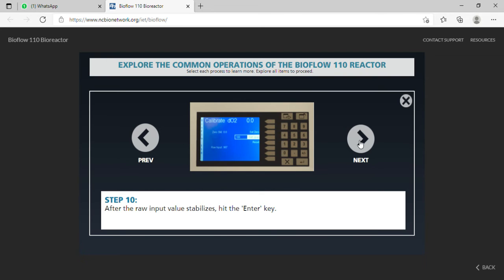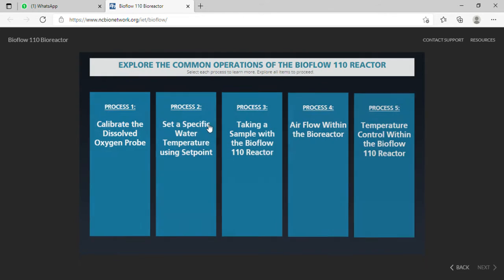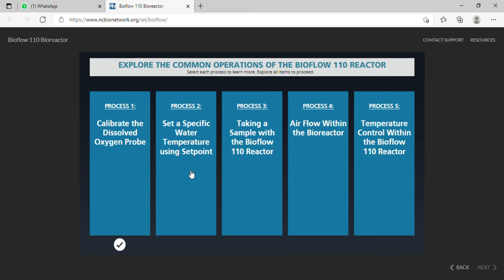Step 10. After the raw input value stabilizes, hit the enter key. Step 11. Select Return to Main on the PCU touchpad to finish the DO2 calibration activity. Step 12. You have now calibrated the DO2 probe. Process 2 is to set a specific water temperature using setpoint.